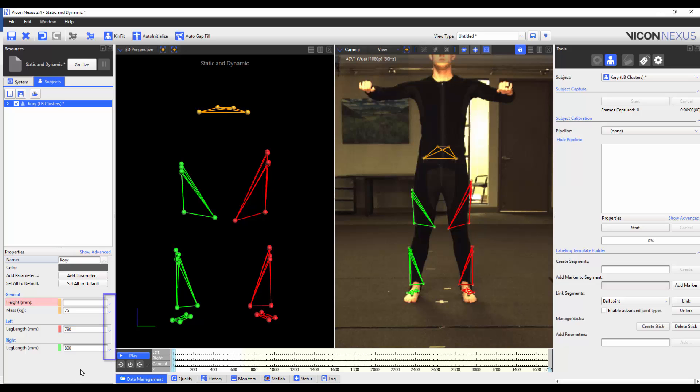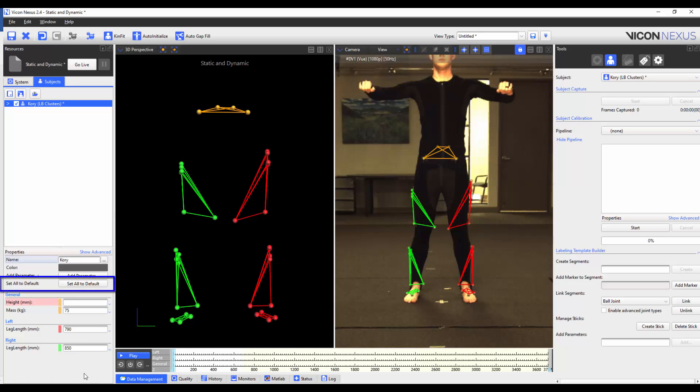Finally, the default value can be set by clicking on the drop-down menu to the side of the parameter and selecting set to default. You can press the set all to default button, and this will set all the parameters to their default values. As you can see, if no default value was set, the value reverts to zero.